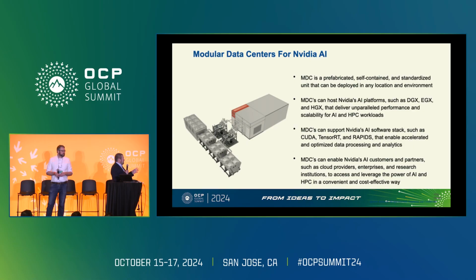Data centers that are very efficient with adiabatic cooling can have a PUE as low as 1.02, 1.03. When you add chilled water, it's going to get to 1.15, 1.2, somewhere down the road. But this is something that can come up in 90 days, so when you order your Blackwell, it's going to take you more than 90 days to get that.